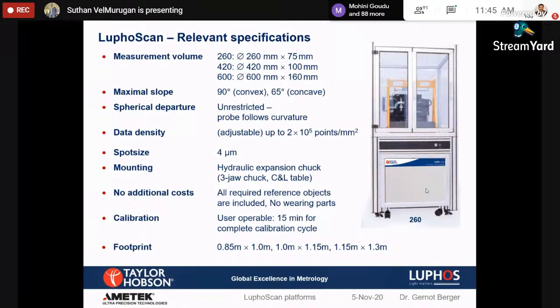With the stylus, if it moves, we have a limitation on the movement of the stylus. The recommended movement speed is about 1 millimeter per second. For example, if you have a 100 millimeter diameter part, it is going to take 100 seconds, roughly more than 1.5 minutes, for the measurement time alone. The alignment time, loading and unloading time are all added on top of that. But as I said, in the LUPHOScan, it is going to rotate at 100 RPM. I'm sorry, the contact profiler is going to take 1.5 minutes for a single trace.